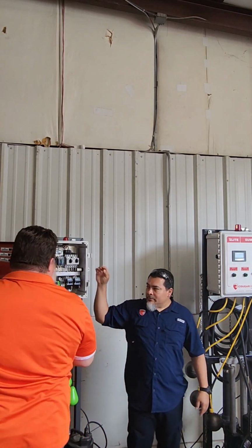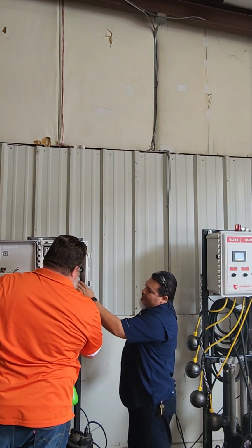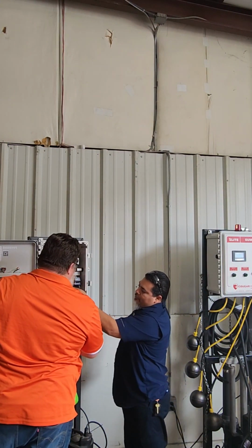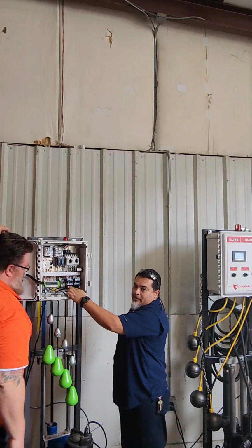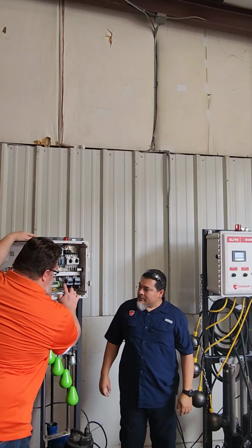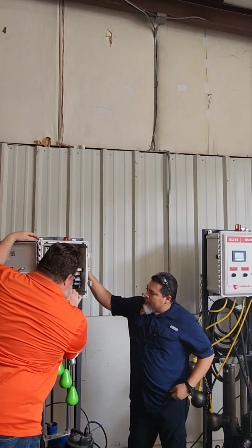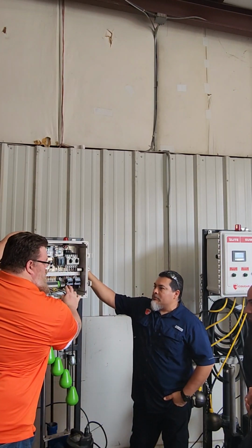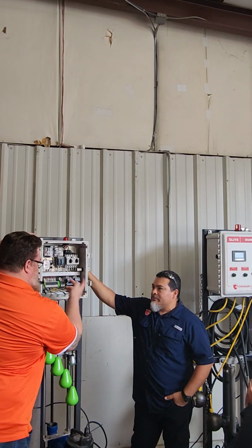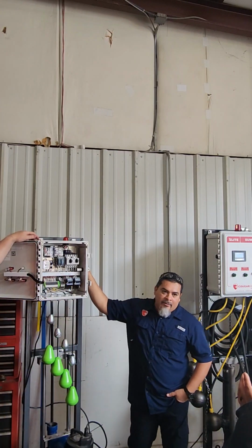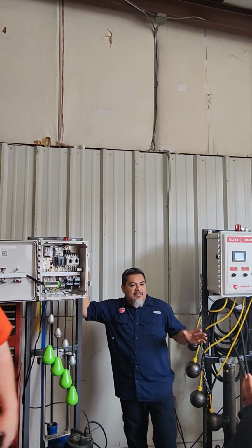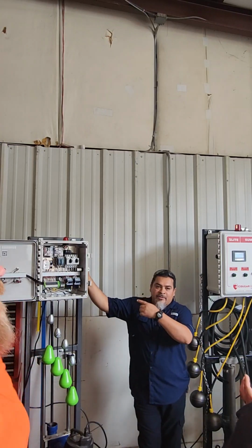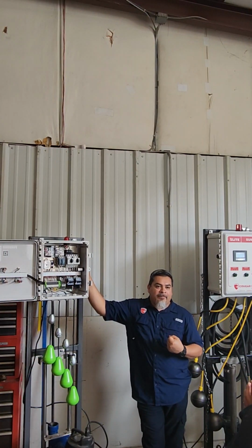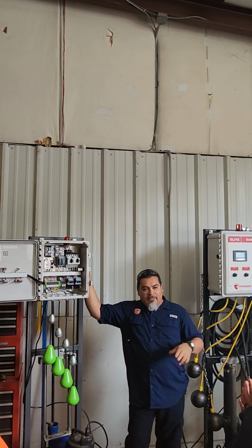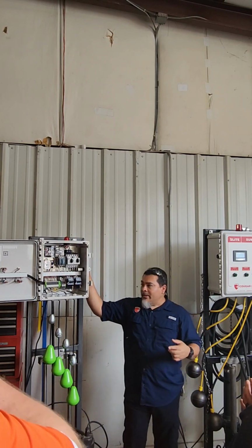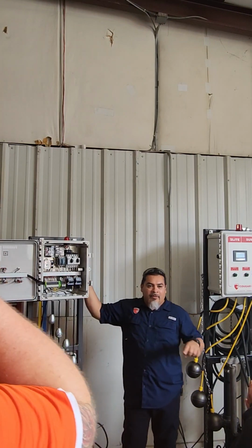What's the difference between the single phase and three phase? Where are you changing leads on this thing? For example, right here, this is your overload, this is your contactor. So whatever's wired here goes to the pump. Yes. So right here you can change. You can go with 1 and 2, 1 and 3, 2 and 3. It doesn't matter. Switch them, and then we'll reverse polarity. Yes. I recommend maybe doing it for like 10 seconds. But if it still trips the overload, then something's really locked up in there. And make sure when it does cycle, you set it back to normal, back to the same rotation. If not, it's going to be running backwards.